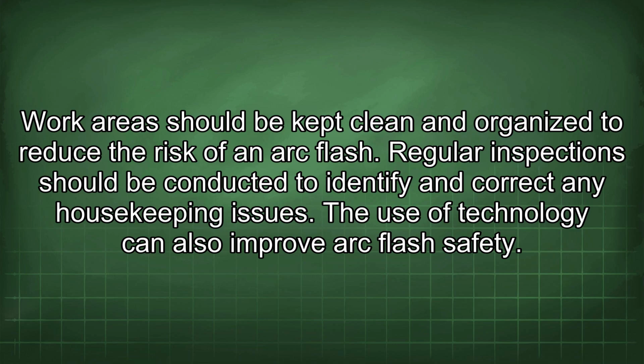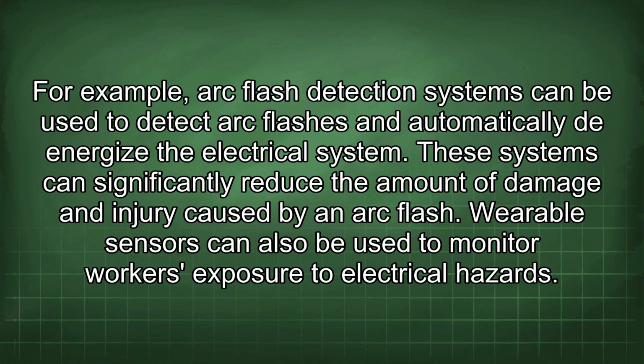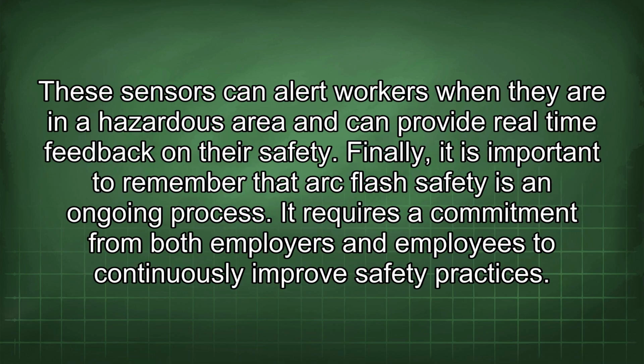The use of technology can also improve arc flash safety. For example, arc flash detection systems can be used to detect arc flashes and automatically de-energize the electrical system. These systems can significantly reduce the amount of damage and injury caused by an arc flash. Wearable sensors can also be used to monitor workers' exposure to electrical hazards. These sensors can alert workers when they are in a hazardous area and can provide real-time feedback on their safety.